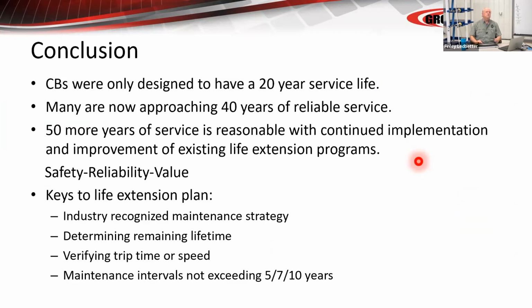Boy, I tell you, we're getting here. Circuit breakers are only designed to have a 20-year life. Now that they got steel bearings in them today, and they're lubed for 20 years. So make sure that beyond that 20-year period, you're doing proper maintenance. Many are now approaching 40 years. They've been in service reliable, but a lot of them have never been called upon to interrupt a fault.